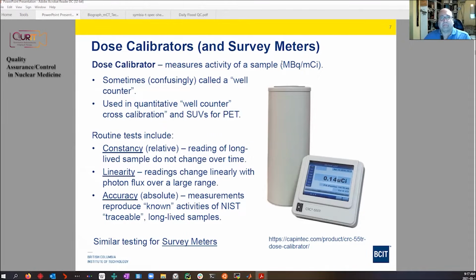So if we're getting a measured physical value out, megabecquerels or millicuries or microcuries, we need to do quality control testing. So just a sample of the tests that are done. Every day, technologists put a set of standard long-lived samples in, and they test the readings to make sure that the reading doesn't change with time. So they just want to make sure there's a constant reading, and it doesn't matter what the setting is. They may have one radionuclide in, and they may have the setting for another one. That doesn't matter. They're just checking whether it changes over time. If it does change overnight or from the day previously, if there are some long-term changes, then that's telling us there's something wrong with the equipment.